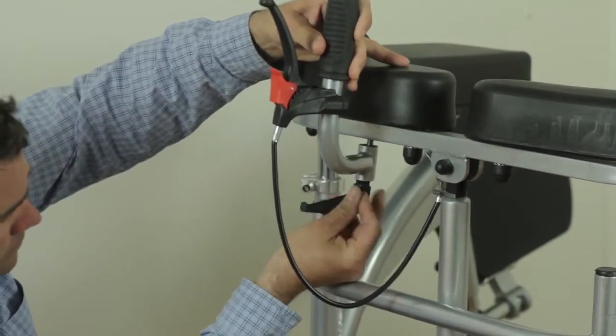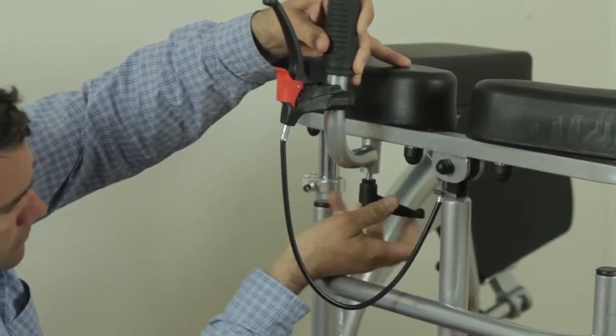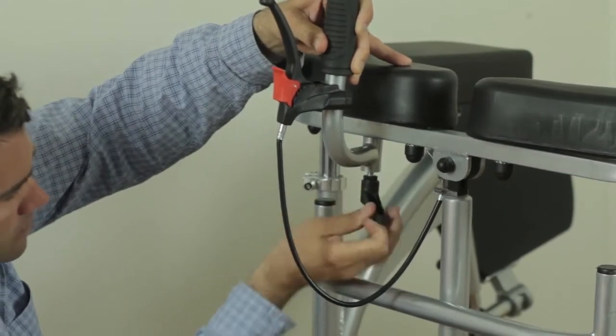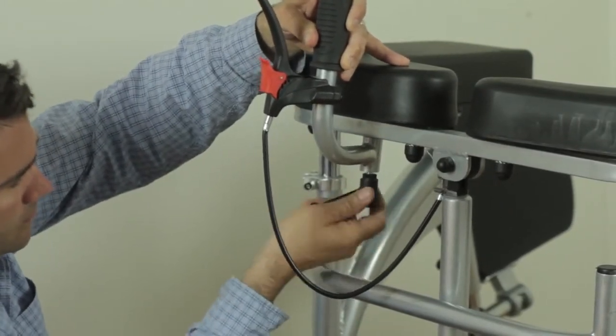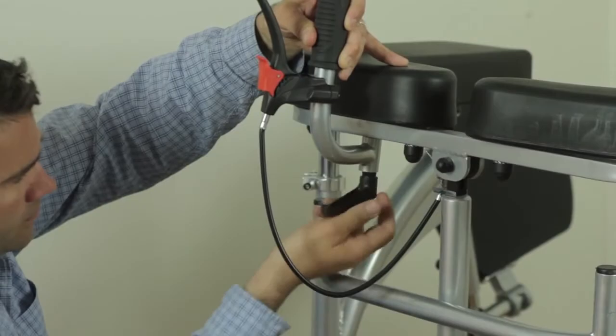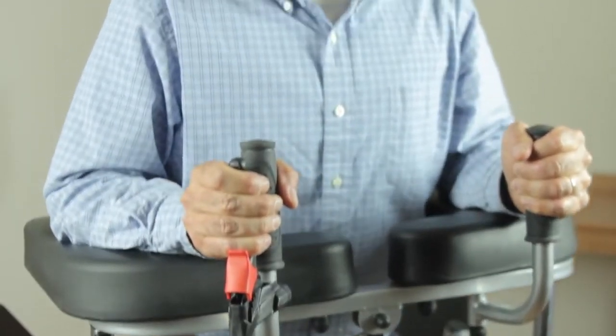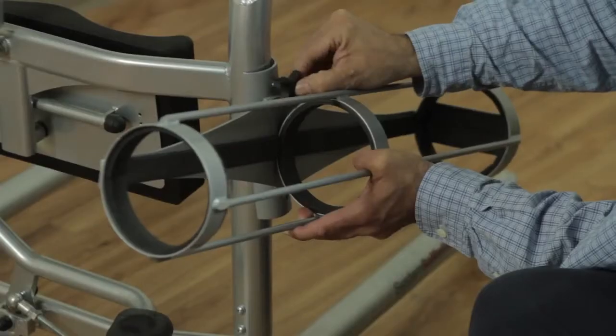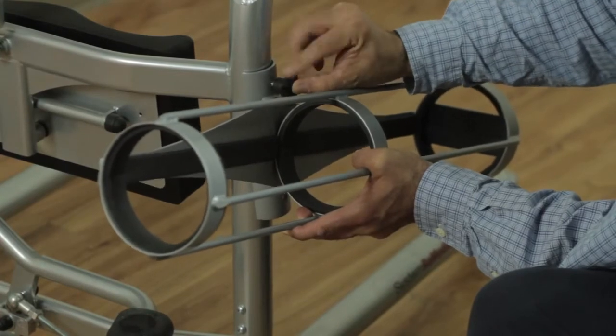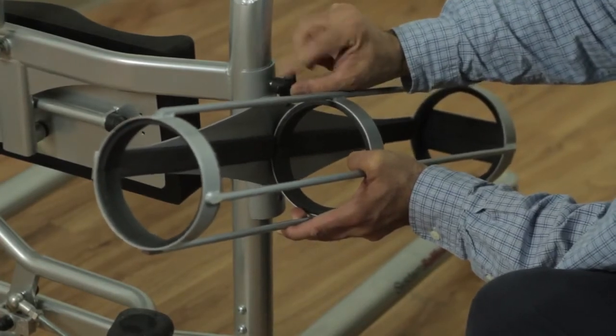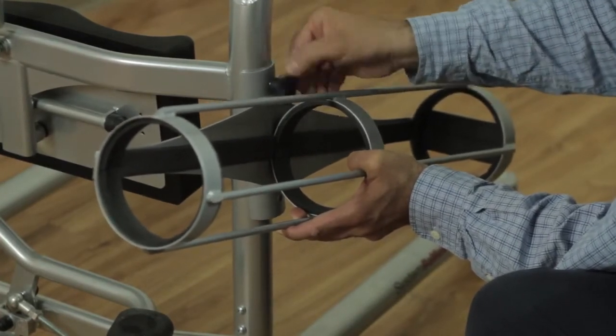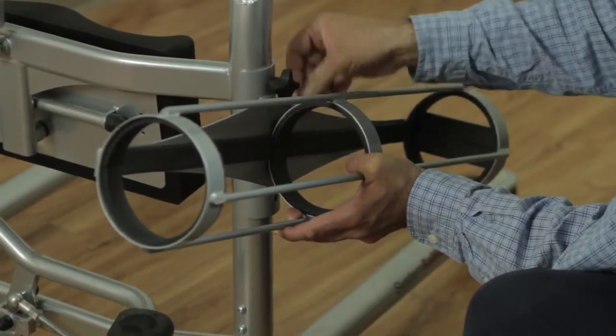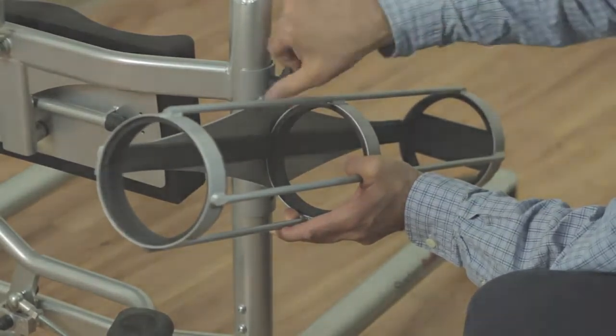Step 1. Roll the unit out of the box. Attach the handles to the RoWalker with the provided locking levers. Make sure to securely tighten them. Loosen the vertical locks and pull the piston activator to ensure operation. If the oxygen tank holders were purchased, use the provided knobs to attach them to the appropriate side. If the optional basket was purchased, hang it on the horizontal crossbar.